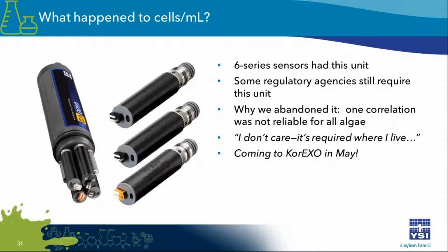Now, I think it was Greg, somebody asked a question about if you've been using the 6 series. Yeah, it was Wilton, I think. Wilton Burns asked if you're using the 6 series and you want to compare data from the 6 series and the EXO. Another feature that we're adding to the software is that you will actually be able to apply the legacy 6 series algorithms to your EXO data. This is something to help folks transition from the 6 series platform to the EXO platform, and what it means is what you used to read on 6 series is going to look exactly like what you're going to read on EXO now. You can choose to apply that platform. My advice, if you have the option, is to start fresh and start generating your data on the EXO platform. And we also find that often there's very, very little difference between the two. It really is dependent on the type of algae you're working with and what your situation is.